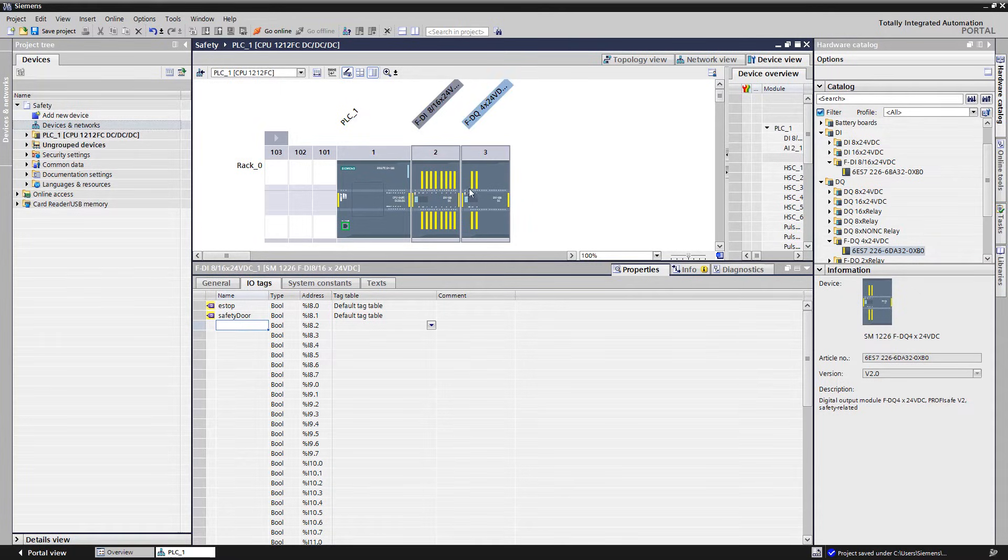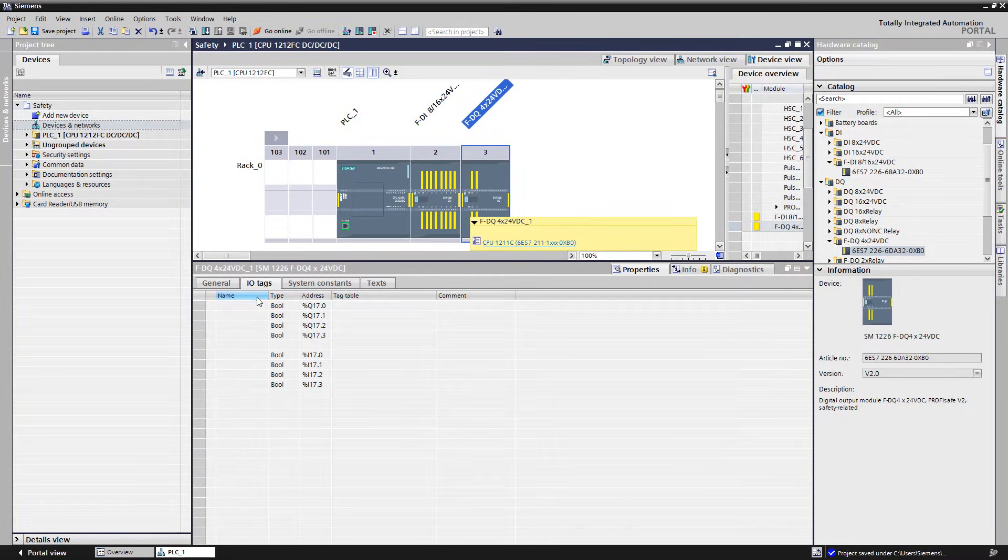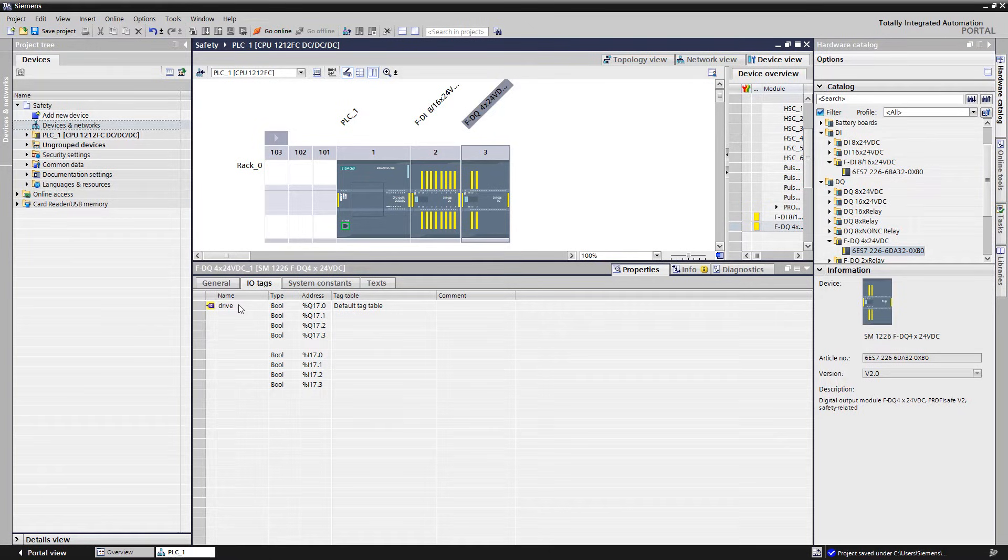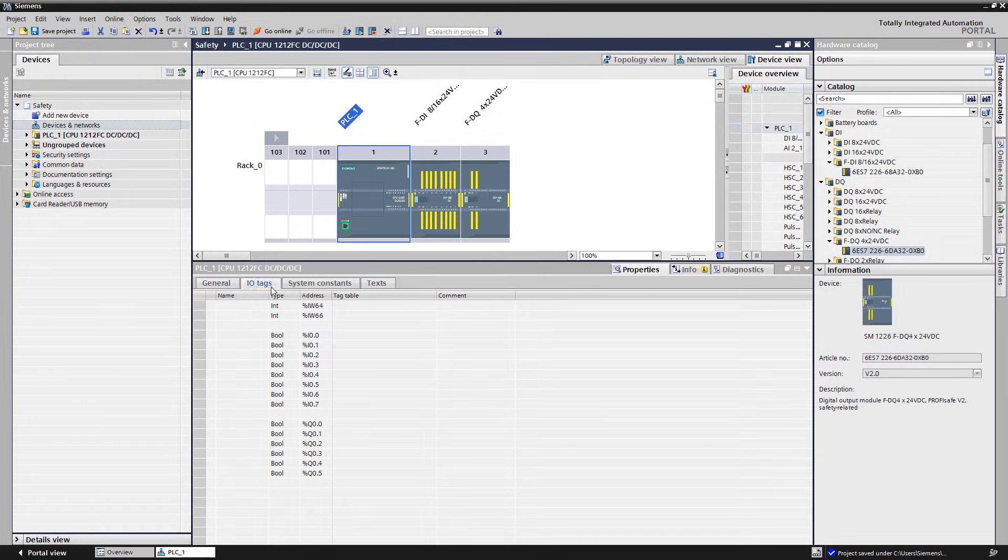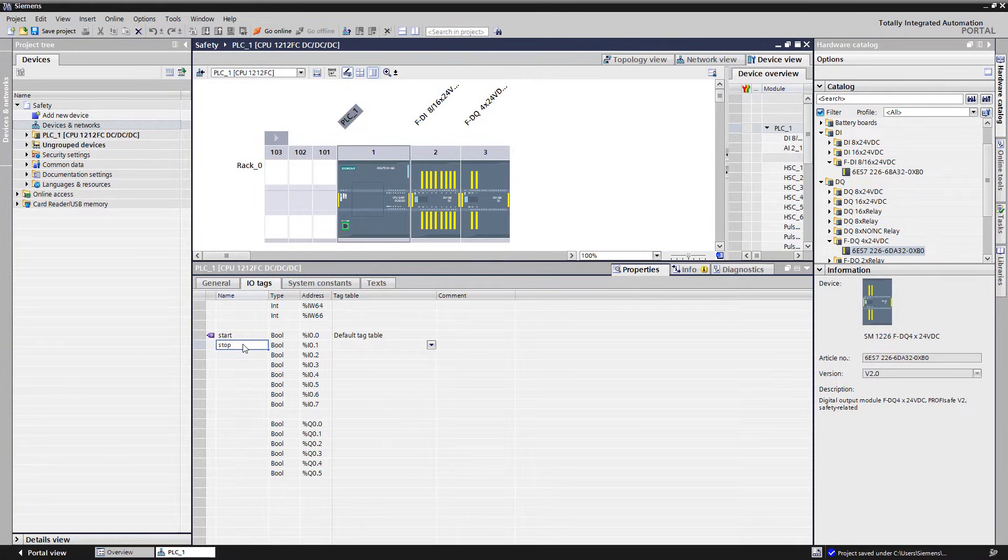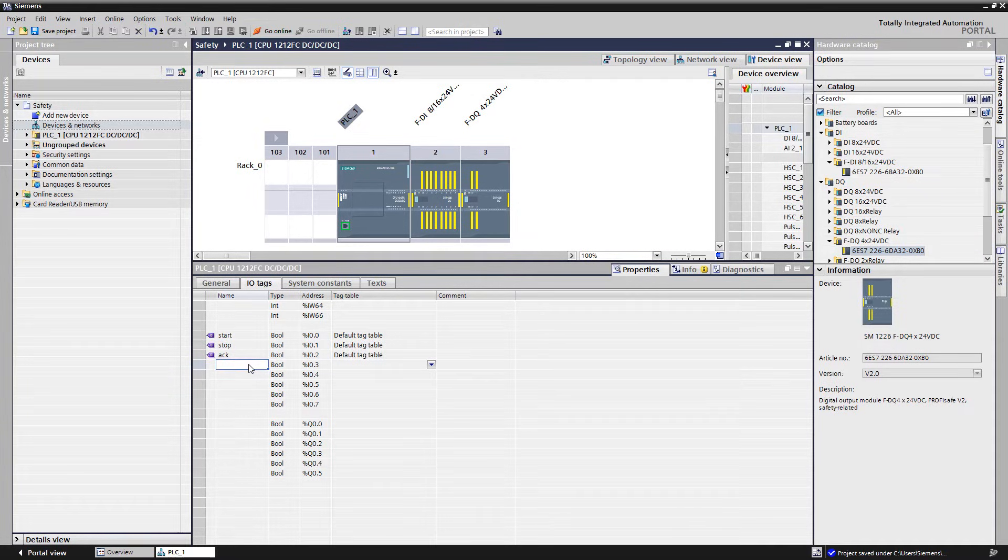The safety related shutdown of the motor starters is performed with a failsafe output. The default parameters of the module do not have to be changed here. Only the variable name for the output has to be added. For the subsequent application, we need the variable names for start, stop, and ack for the acknowledgement, which we enter in the list of the IO tags of the CPU module. The hardware configuration is finished now.